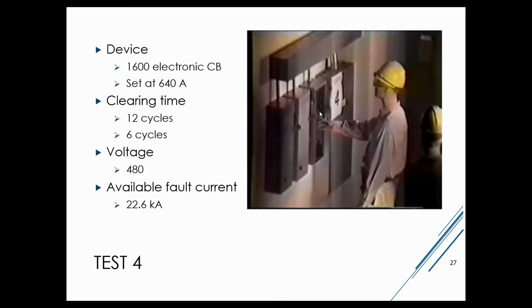They were creating the arc event inside the disconnect enclosure where the mannequin's hand is. And it cascaded up into the wireway, which you'll see in the upcoming photos and video, hopefully, if that all works out today. So it was a 480 volt circuit, and there were 22,600 amps of available fault current at this location.